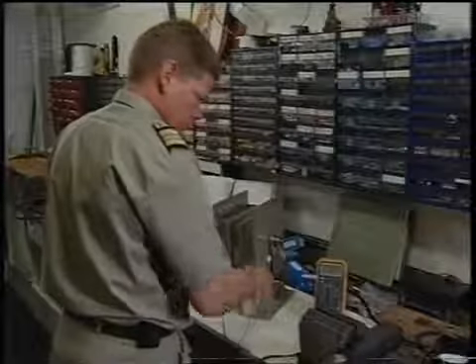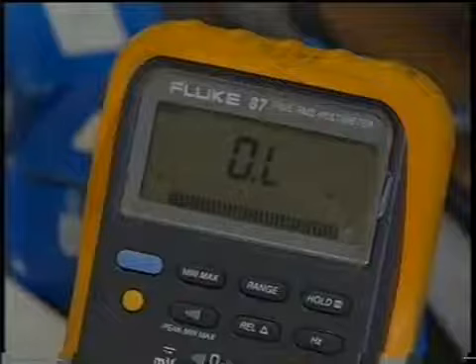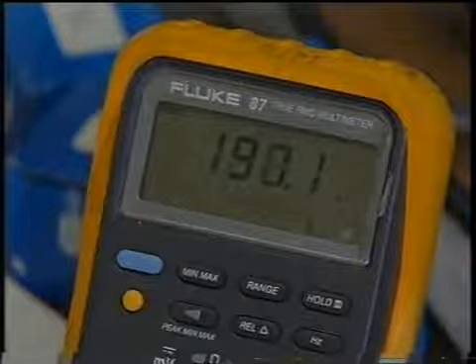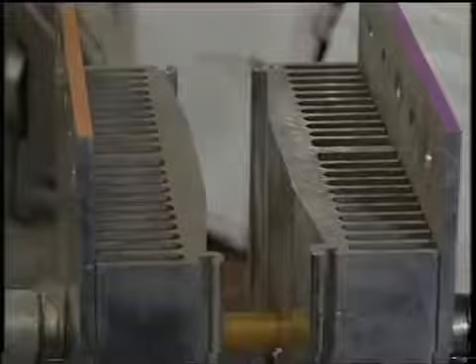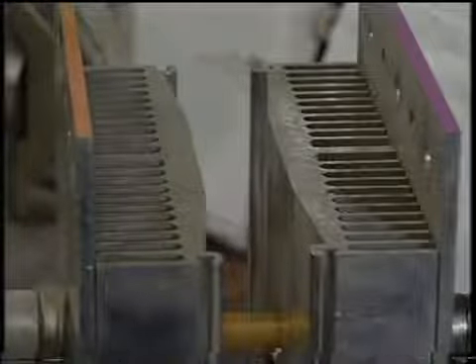A perfect switch has no power loss, as it will have 0 resistance when closed for current flow and infinite resistance when open. A conducting thyristor develops about 1.2 volts between anode and cathode, so when carrying, say, an average current of 1000 amps, the power loss is 1200 watts. This heating effect is rapidly dissipated by a finned aluminium heatsink to avoid thermal breakdown.